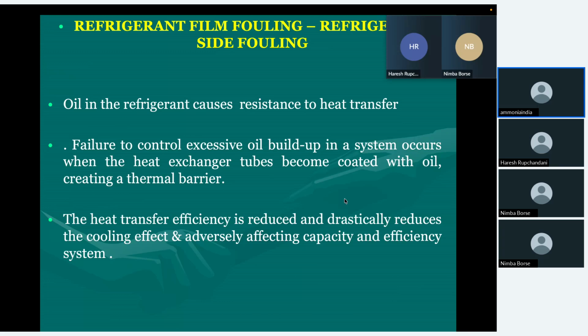The ammonia and oil travel throughout the system, and everywhere we have to have oil drains, at the oil separator, at the receiver, at the evaporator. So instead of that, if you use a demister pad SS oil separator, your oil carry forward will be reduced and your fouling will also reduce. The heat transfer efficiency is reduced drastically if it is fouled, and it reduces the cooling effect.